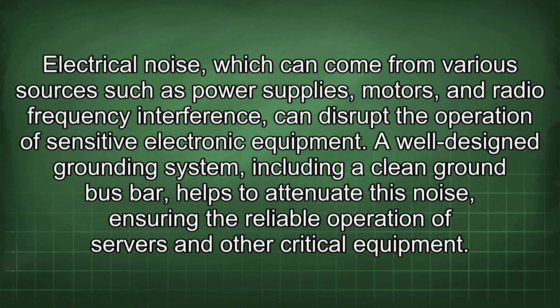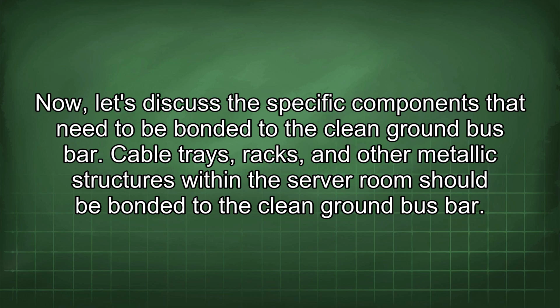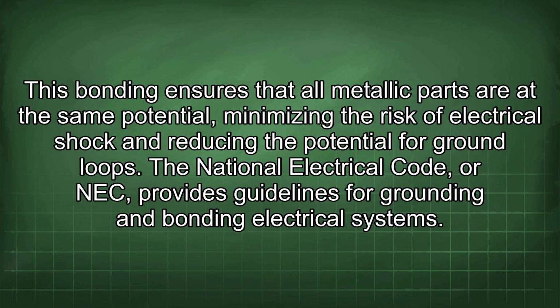Electrical noise, which can come from various sources such as power supplies, motors, and radio frequency interference, can disrupt the operation of sensitive electronic equipment. A well-designed grounding system, including a clean ground bus bar, helps to attenuate this noise, ensuring the reliable operation of servers and other critical equipment. Now let's discuss the specific components that need to be bonded to the clean ground bus bar. Cable trays, racks, and other metallic structures within the server room should be bonded to the clean ground bus bar. This bonding ensures that all metallic parts are at the same potential, minimizing the risk of electrical shock and reducing the potential for ground loops.